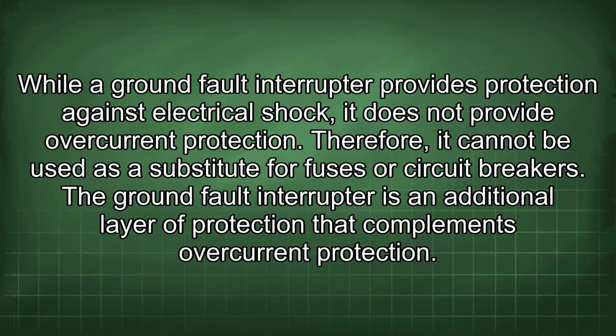While a ground fault interrupter provides protection against electrical shock, it does not provide overcurrent protection. Therefore, it cannot be used as a substitute for fuses or circuit breakers. The ground fault interrupter is an additional layer of protection that complements overcurrent protection.